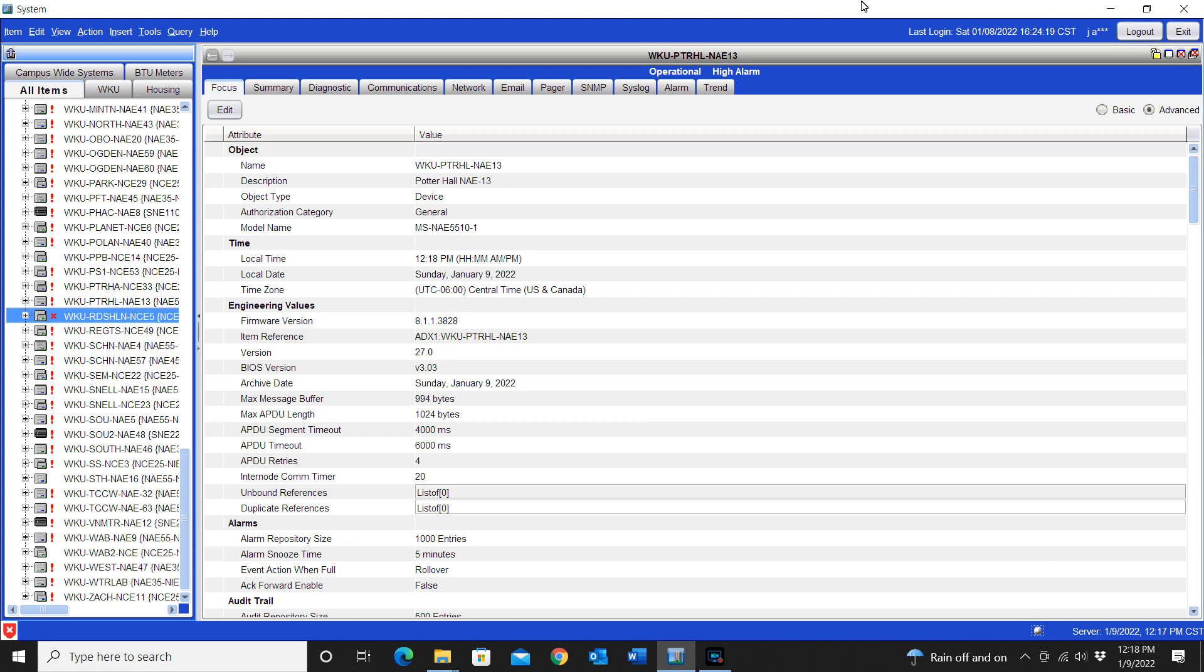Now we're going to be talking about something here in a few minutes that will play into some of the potential communication issues depending on the version of Metasys you're running as well as the way your IT security is. If you are able to browse to the device using your SCT, if you have SCT on your local laptop, that's a good thing. It's a very useful tool. Try browsing from your server to the device.